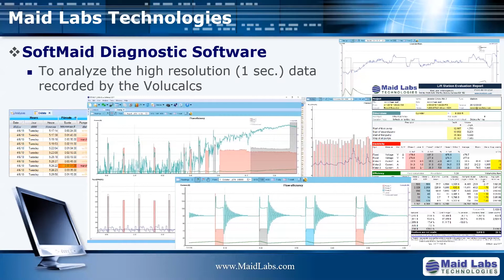Not too long ago, I decided to analyze the actual pump capacity and runtime of over 150 lift stations, comparing the variation of one versus the other. When you have two identical pumps within the same lift station, you'll see your pumps never have exactly the same capacity or flow rate, and they never have exactly the same runtime. I can tell you that for every percentage of flow rate variation, you get twice that percentage of runtime variation.